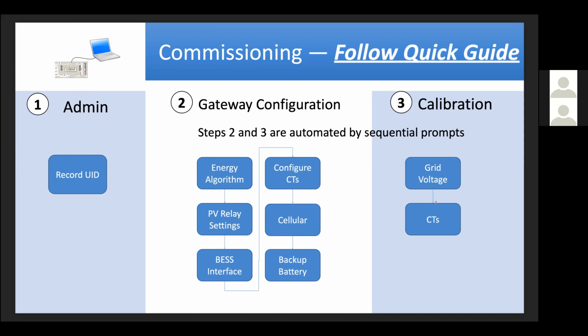And the next step would be to do a backup loads test: kill main power, the main breaker, kill the power to the main service panel. Observe the battery has a 4-second delay, goes into off-grid mode, and powers the backup loads panel. PV would then turn on in the backup loads panel 5 minutes later. You would see that the system is then working in an off-grid mode.